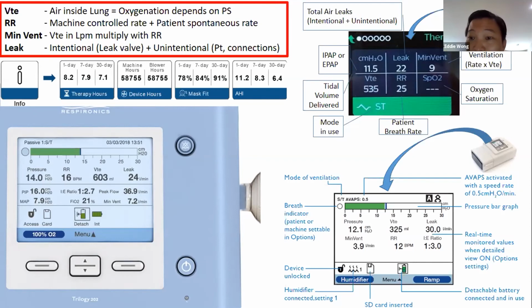So when you see the low minute ventilation alarm, no matter whether you're lying down or not, you have to suspect either the patient is not performing any effort to breathe, that's why the rate is dropping, or maybe the circuit is disconnected, that's why the rate becomes 0. Or if this is a volume problem, you need to check whether there is an air leak due to circuit disconnection, or due to any mask interface loosening, causing excessive leaks that cause the volume to drop.